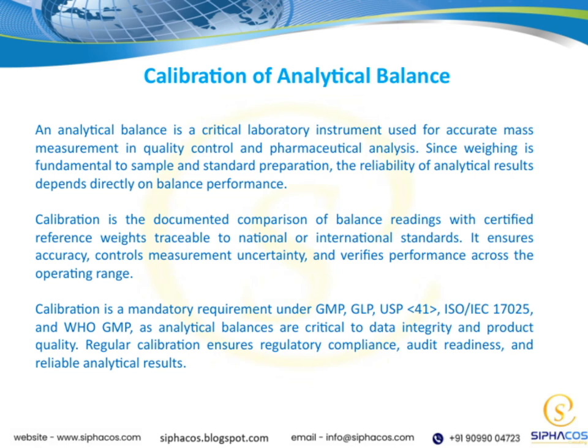It involves comparing the balance's readings against certified reference weights, which are traceable to national or international standards. This process ensures that the measurements are accurate, helps us control measurement uncertainty, and verifies that the balance performs well across its entire operating range.